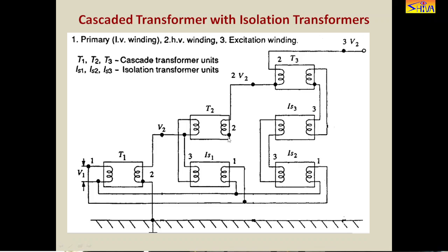The second stage is kept at potential V2, that is the output voltage of the first stage. The output terminal of the second stage is connected to the body of the second cascaded unit, which is kept on insulators and is isolated from the ground at potential V2. Similarly, the third unit T3 is also kept on insulators, and the output of the second stage is connected to its body, so the third stage is at a potential of 2V2 with respect to ground. The output at the second stage is 2V2 and at the third stage is 3V2 with respect to ground.